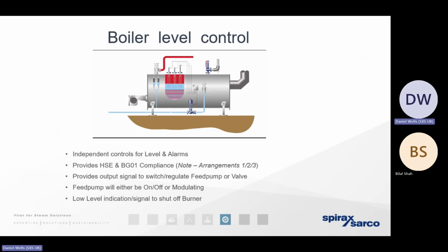So other things we want to think about in the boiler is the way the water level is being controlled. Think of that steam boiler as being a giant can of Coke. We fill it 80% full of water, we lie it on its side. When that happens, if we know the exact water level within the boiler, we know the surface area of the water. So we know the velocity that the steam is leaving the boiler at. Now, if the water level fell or rose significantly, that surface area is changing, which means the steam can be leaving the boiler at a different velocity. And in extreme cases, it can carry more of the water out of the boiler and into the pipework. And that's really going to create those inefficiencies and those mechanical issues we spoke about.